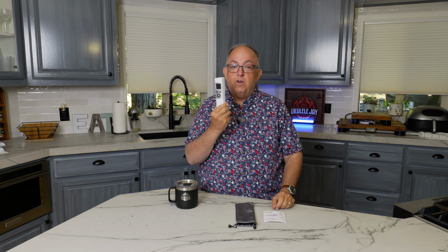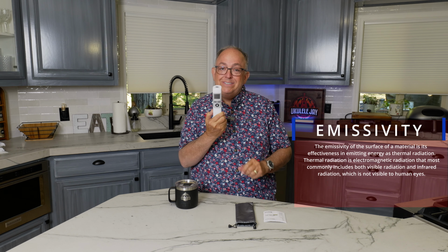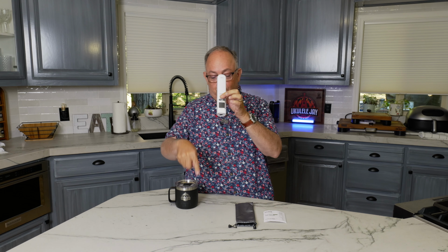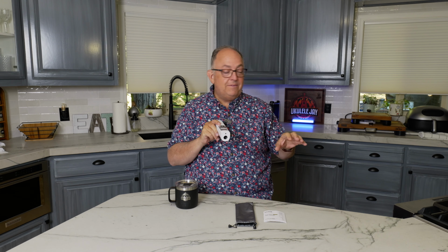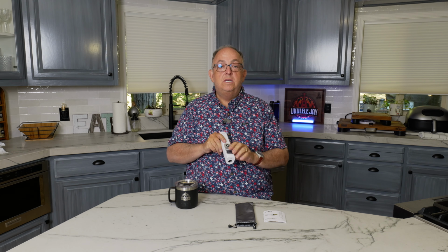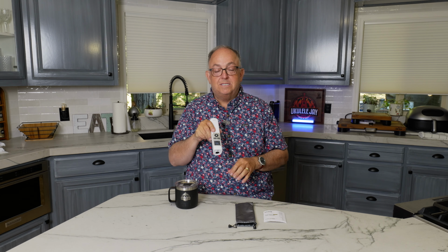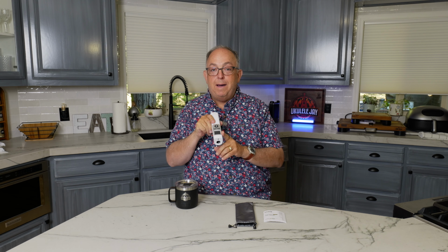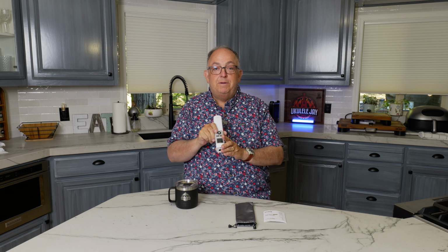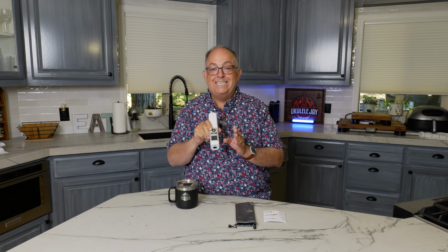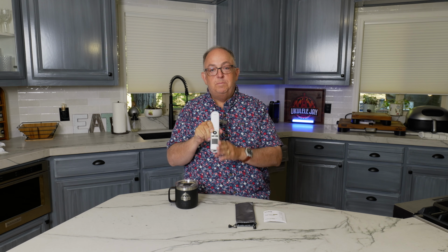Well, there's a feature called emissivity, which adjusts the reading for the surface you're scanning with the infrared. Emissivity is different on different surfaces—metal, steel, plastic, stone. So if you're checking a pizza stone versus a steel surface, the emissivity isn't the same, and you want to make sure it's set correctly. Many other infrared thermometers only use one setting, but if you want real accuracy, being able to change that setting is key, and this one actually has that ability.